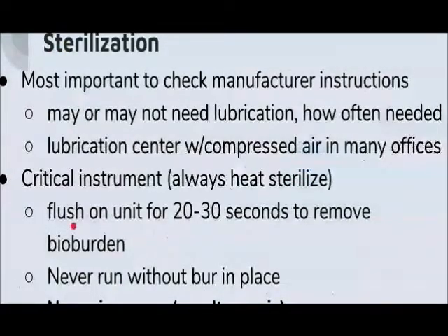All right. So one of our duties, or one of our largest duties around handpieces, is making sure that we know how to maintain them. And we talked about the fact that handpieces cannot be used in dry heat sterilization because it's too hot. And they should also never go in the ultrasonic. So they don't like to go swimming. So you never immerse them in liquid.